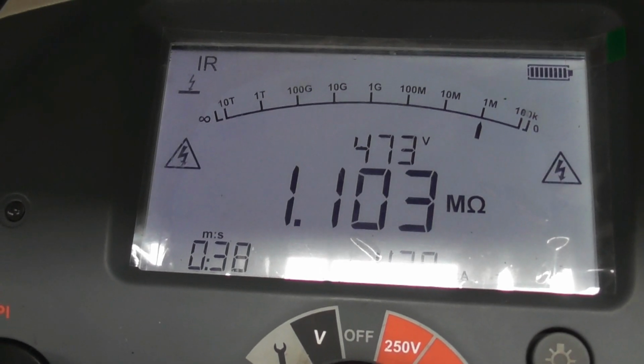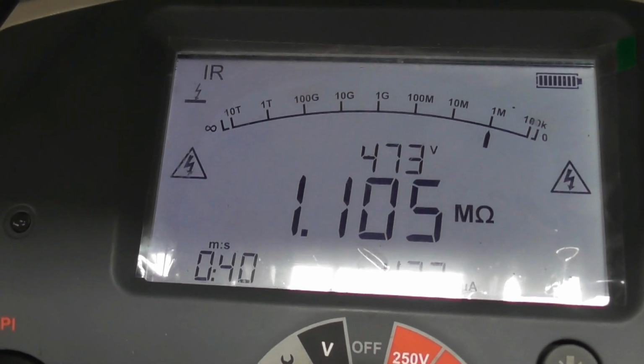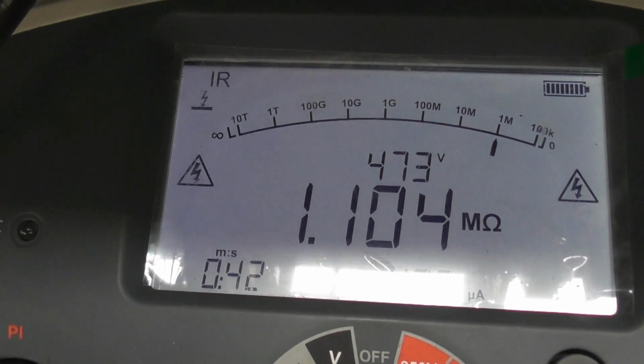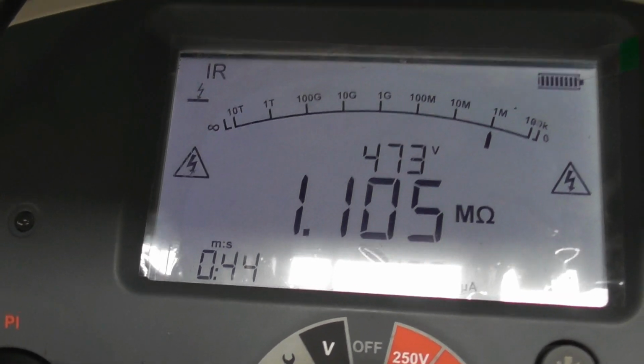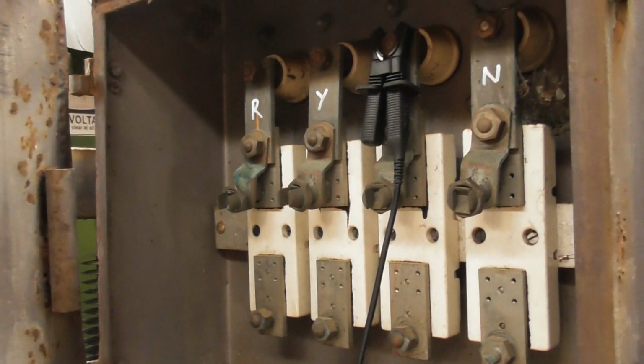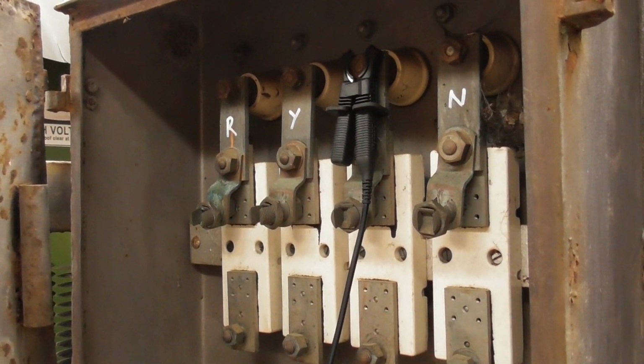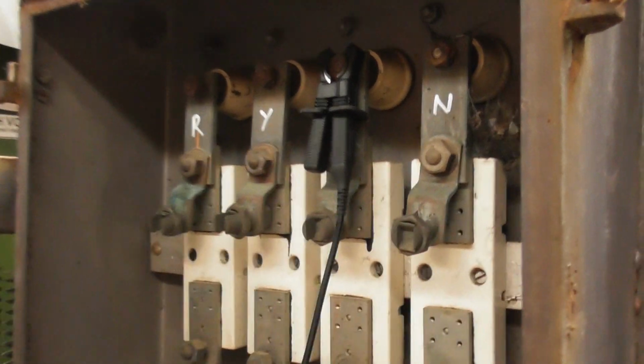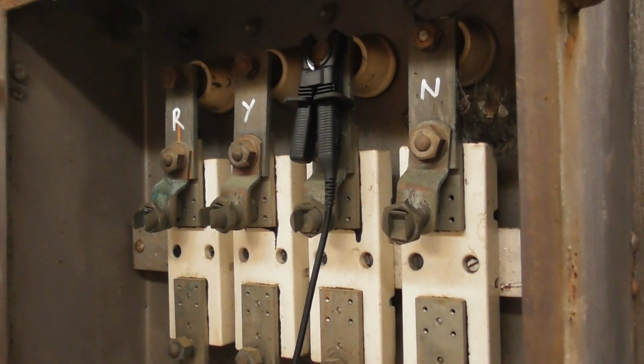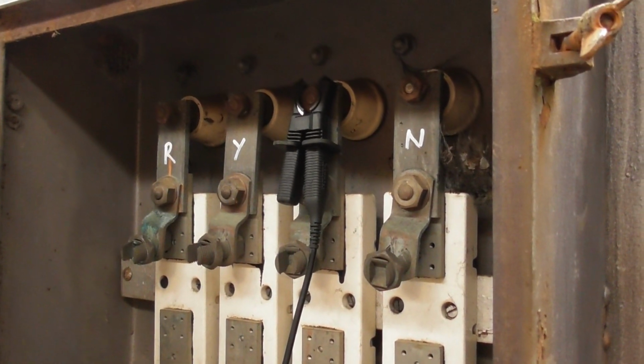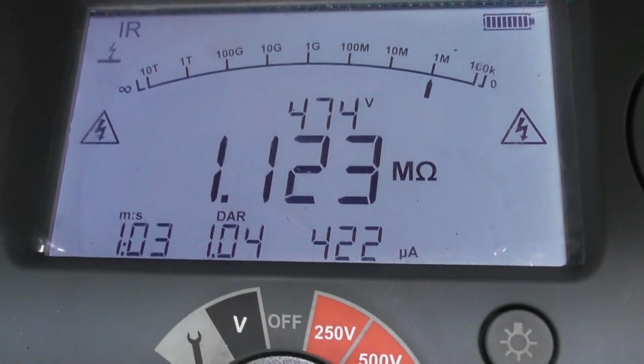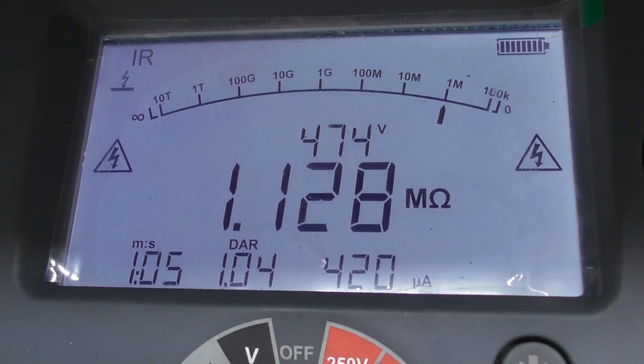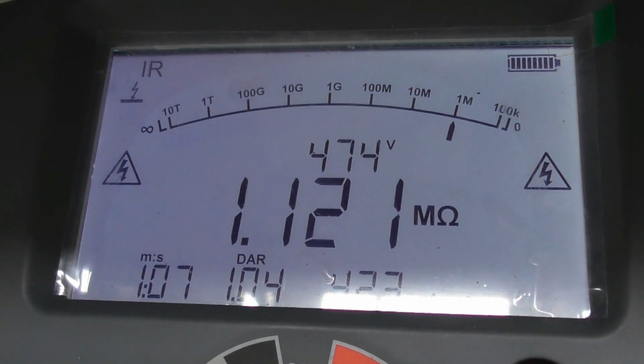Okay, 1 megaohm. This is a 500 volt test. It doesn't even make 500 volts. Transformer could have a fault in it. I connected to one of the phases, so it's a star here, but there's no link on the neutral and the earth. Again, dirty bushings, leakage and stuff. So, quick 500 volt test and do that for about a minute, and that's about 1.1.